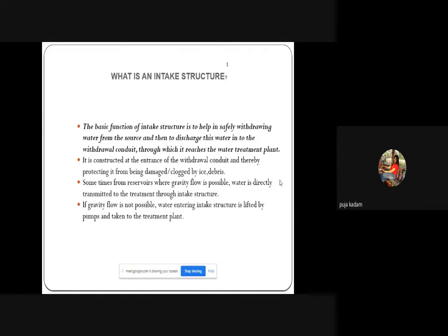An intake structure's basic function is to safely withdraw water from the source and discharge it into the withdrawal conduit — technically a pipeline — through which it reaches the treatment plant. It is constructed at the entrance of the withdrawal conduit, protecting it from damage or clogging by ice or debris. Sometimes, from reservoirs where gravity flow is possible, water is directly transmitted to the treatment plant through the intake structure.